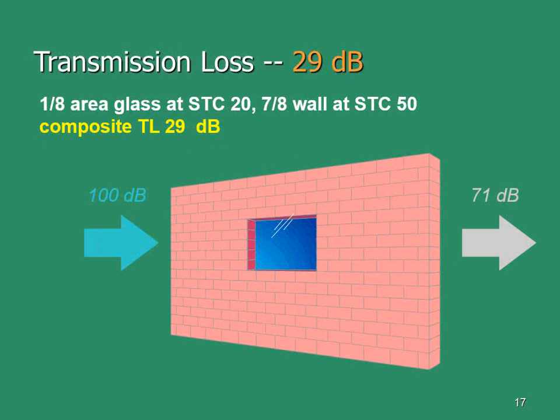If you have a wall or enclosure rated for 50 decibels and it's got 1% open area, that isn't much, but you can take 15 or 20 off that rating. Look at this wall: not even counting the doors, but the perimeter of the doors, the junction boxes for controls, the fire alarm, the clock, all the electrical boxes, that adds up to more than 1% of this wall. So if I design this wall to stop 50 decibels and we put this many penetrations in it, I'd consider myself lucky to get 35 instead of 50, more likely 30, from here to the outdoor space.